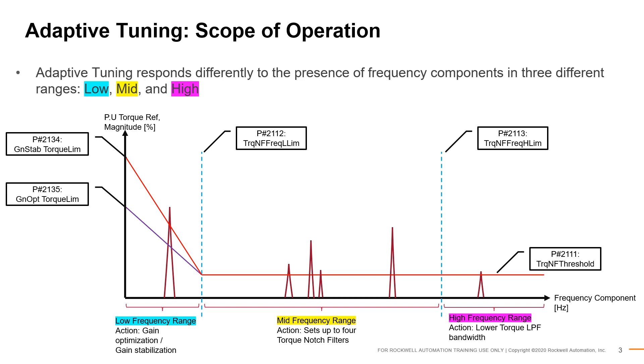In the mid frequency range, the available action is the automatic setting of four notch filters on the torque reference path. A system's characteristic resonances are excited by specific frequencies in the reference signal. A properly configured notch filter removes such excitation components and only such components. This eliminates the resonance excitation, allowing the machine to operate much more efficiently.